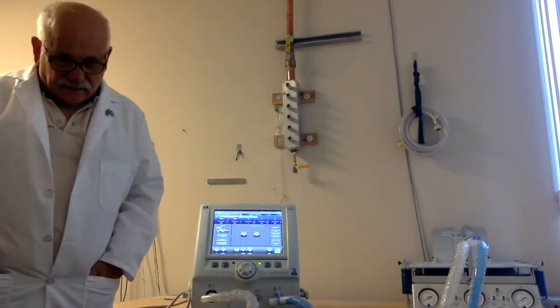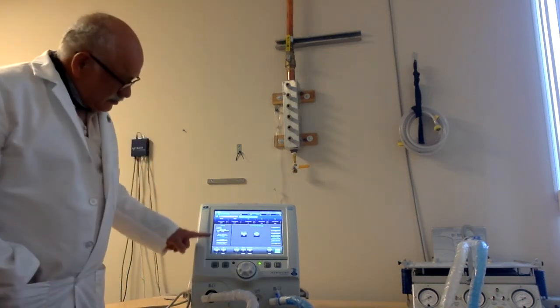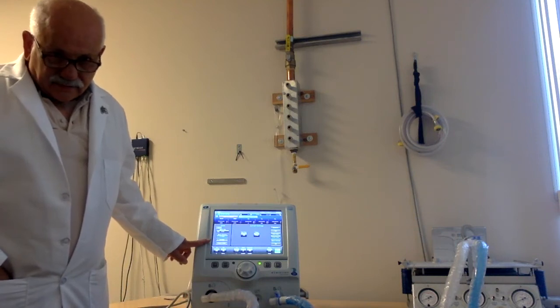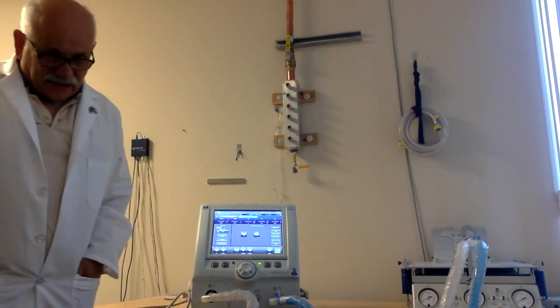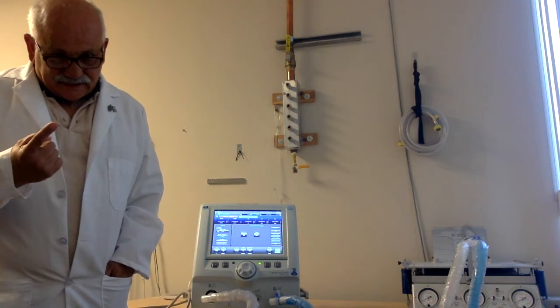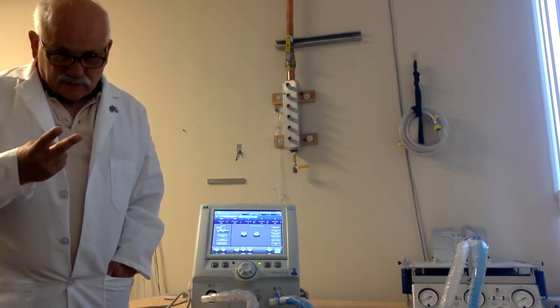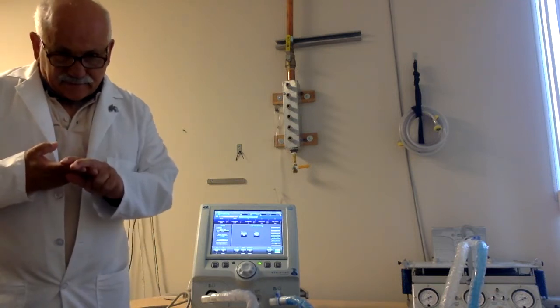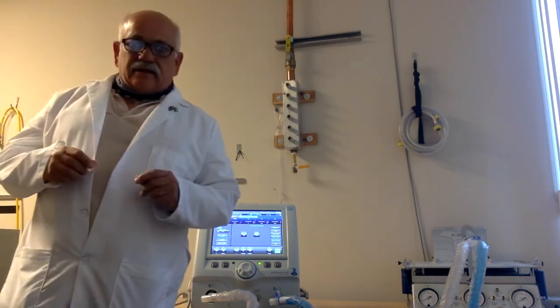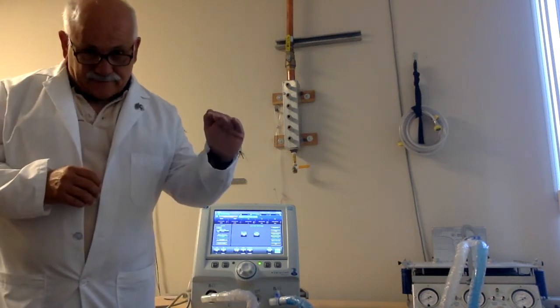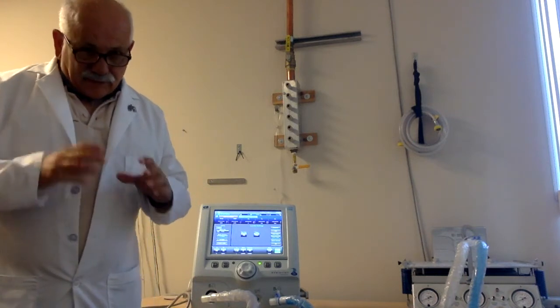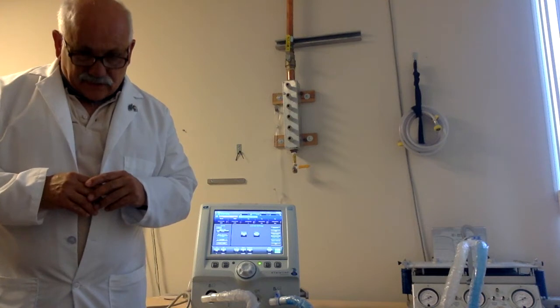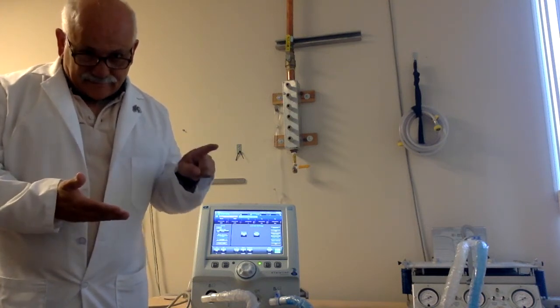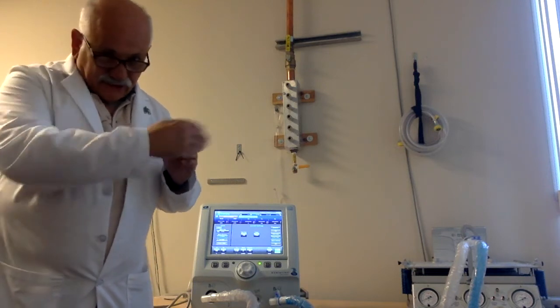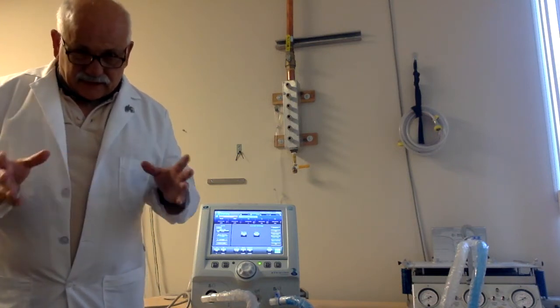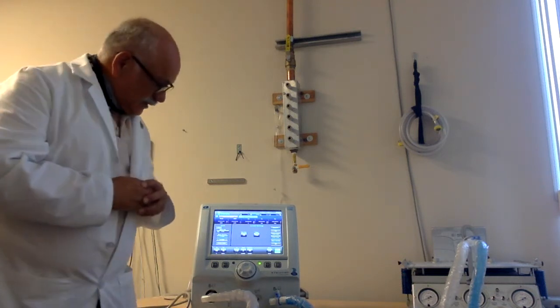This ventilator has a rich set of modes of ventilation, and these modes are organized according to the American Thoracic Society's taxonomy. We know that patients breathe spontaneously, that when we want to, we control their ventilation, and then there's the mix between that called SIMV. We also know that all ventilators either target internally a pressure level or a volume level. So the breath types which fall under the mode allow you to choose pressure-based breaths, where you're targeting a peak pressure, depending on the derivative of the mode, how long that pressure is maintained. You're also allowed to choose a tidal volume, if volume ventilation is what you're used to or comfortable with.